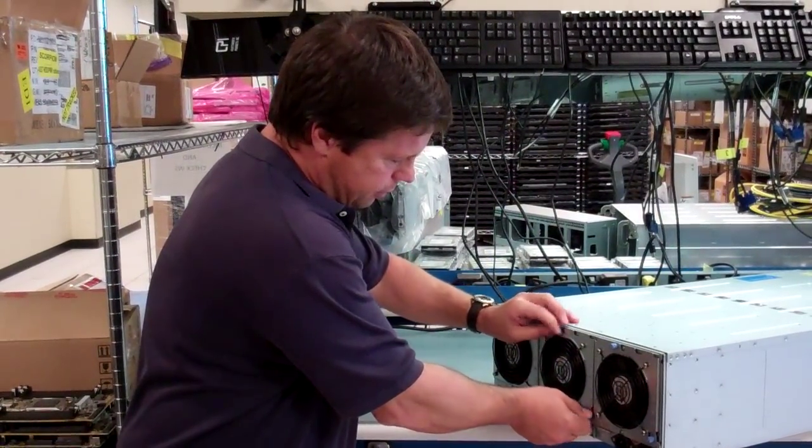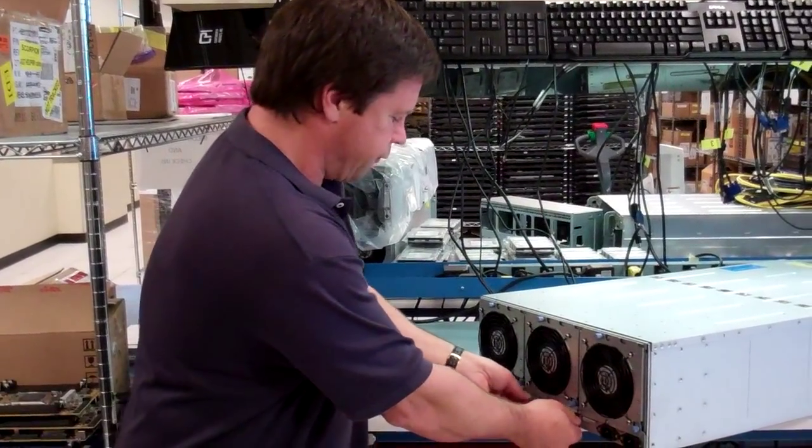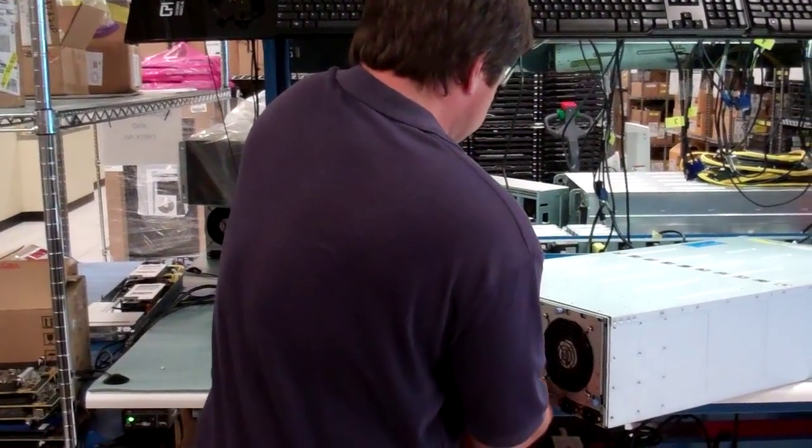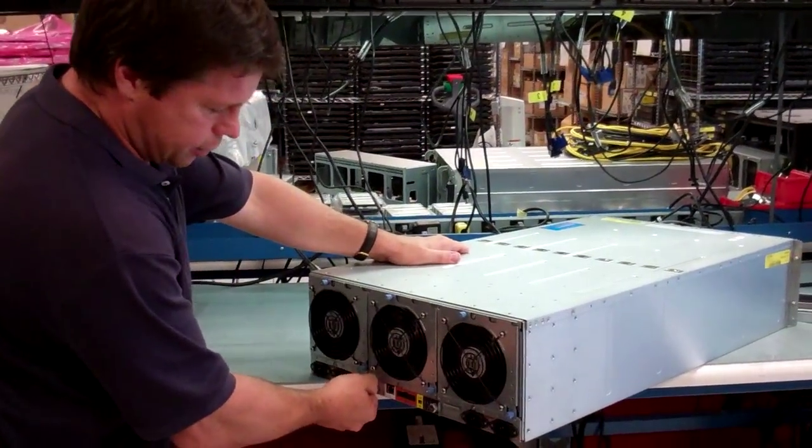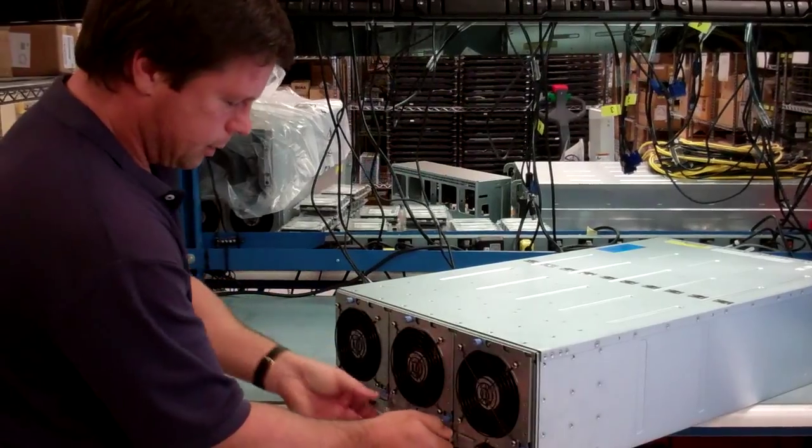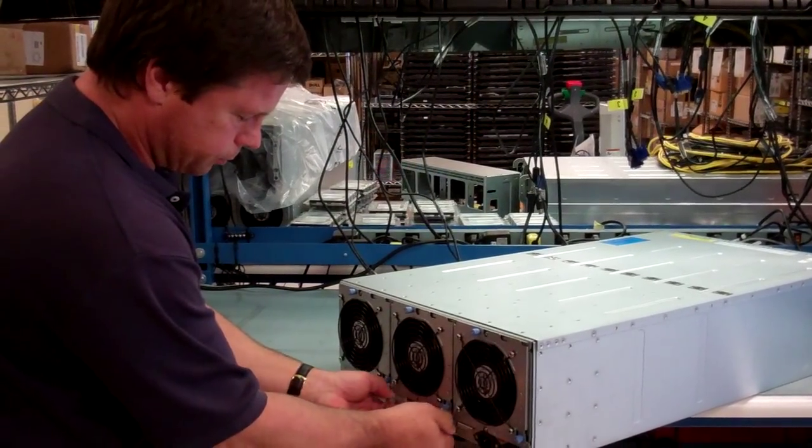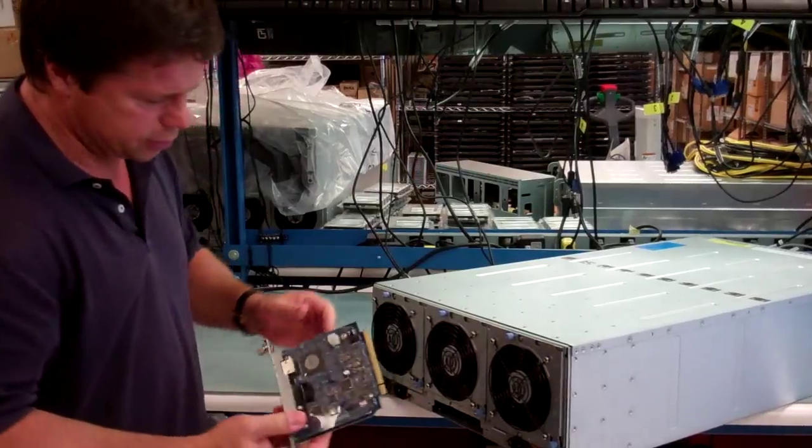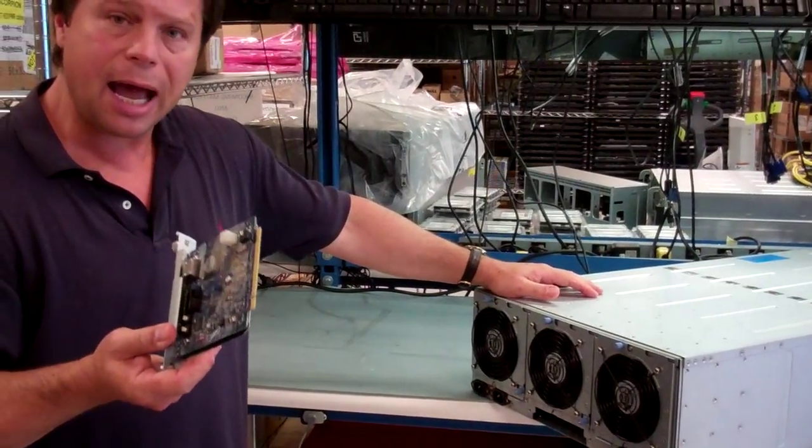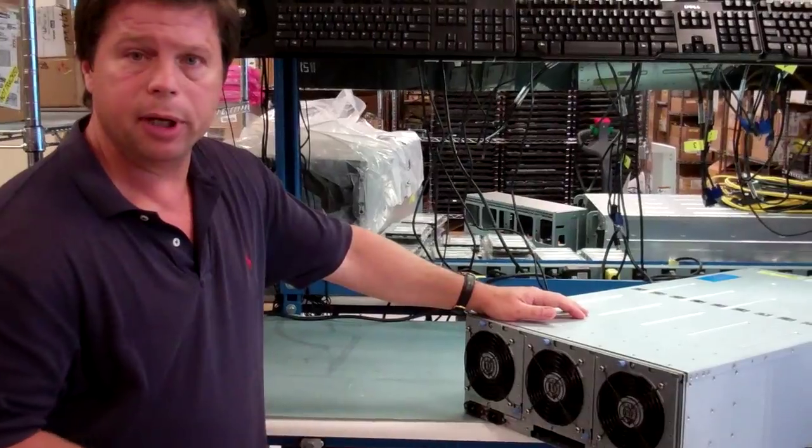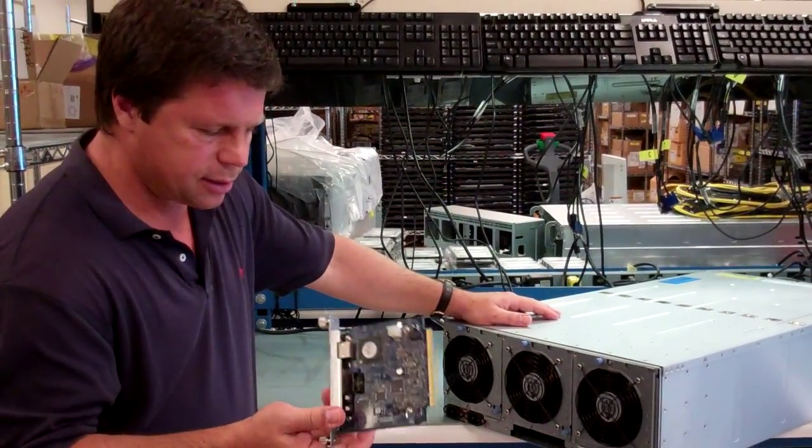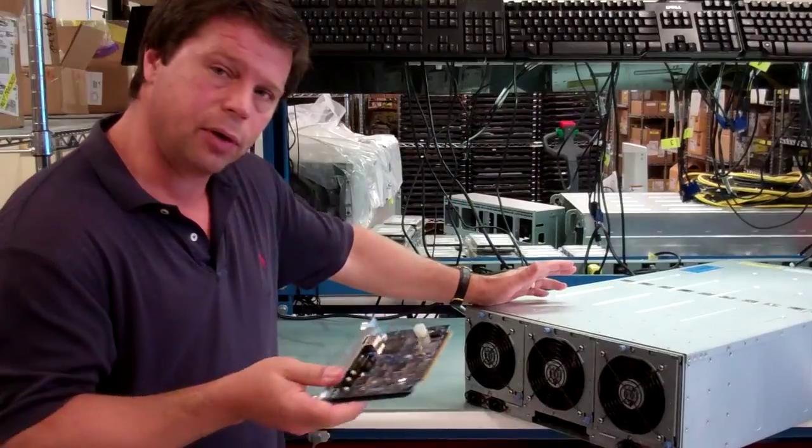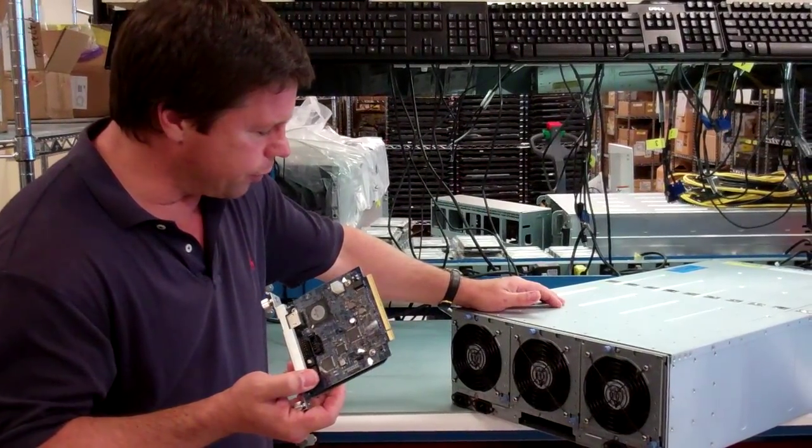The other thing that we have that is accessible through the rear from a serviceability standpoint is our little chassis control or fan control board. And again, tool-less. Real simple. When this is out and the box is still running, all the fans will spin up to max speed. But this is really the only thing in the back that you'd ever have to service.